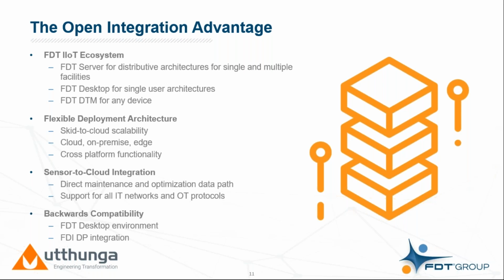And the topic that we're often asked about is the FDI device package. As you may be aware, the FDT Group is a co-owner of the FDI specification. And we do, on the desktop environment in particular, have the ability to integrate the FDI device package into that same environment. So not only can you mix prior versions of DTMs, you can also bring in FDI device packages as part of the mix. And that's due to special DTMs offered by some of our members that will directly process that device package and present it within the FDT environment. So you get basically a universal platform regardless of what configuration methodology you have.